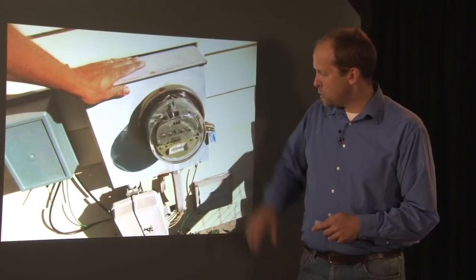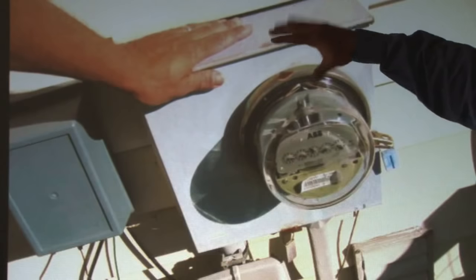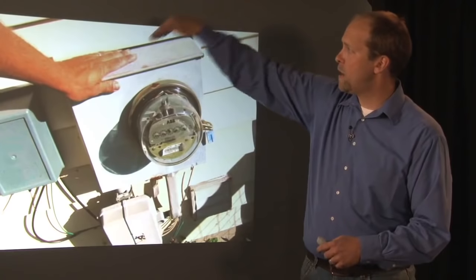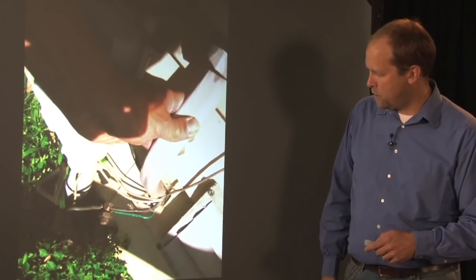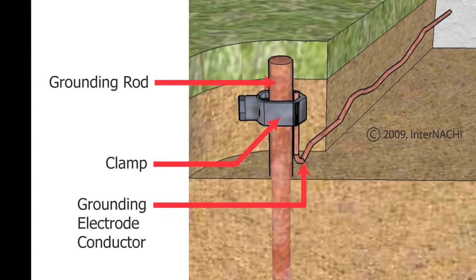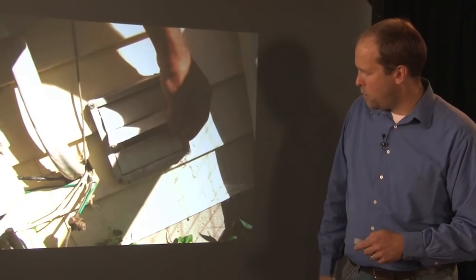Other components. The electrical meter - I put my hand on top just to show my client I tried to move the box away from the house. On older homes I find that the conduit has pulled the meter off the house, now loose and allowing water to penetrate. The condition of the sheathing around the line going into the house is part of my inspection. The grounding wire goes into the vegetation - I know it's installed but can't see where it terminates. Phone and cable noted. That's a sensor for the water meter; the water meter is inside and can be read from outside. The dryer exhaust seems clean.